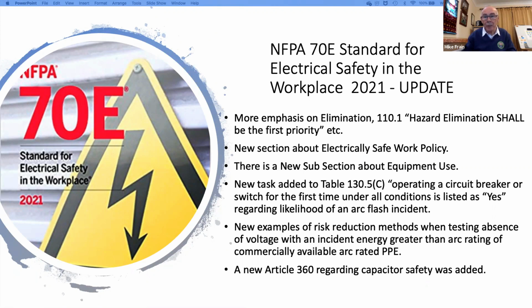It's not as big as people think it is. I mean, it is actually only 19 pages on the safety related pages, but it is predominantly about hazard elimination and being the first priority. And this has been brought right to the forefront within the document itself. And there are new examples of risk reduction methods in there when testing absence of voltage, which I referred to earlier, and also within the informative annexes, there's a new article regarding capacitor safety, which I found very interesting indeed.